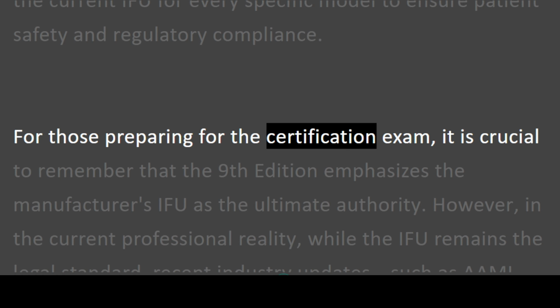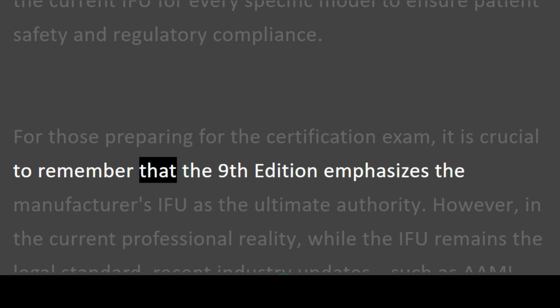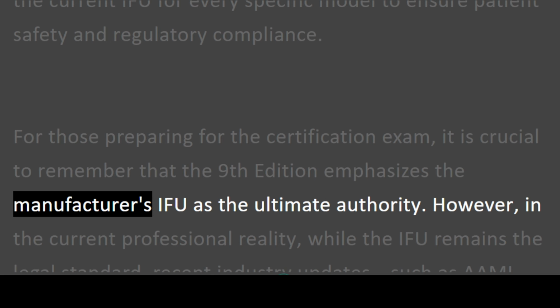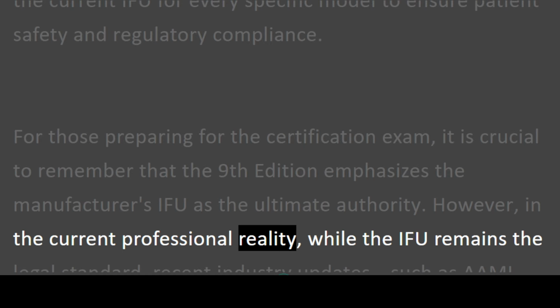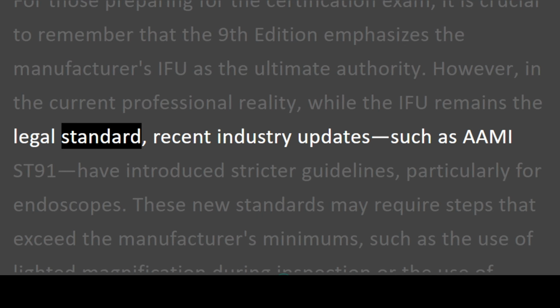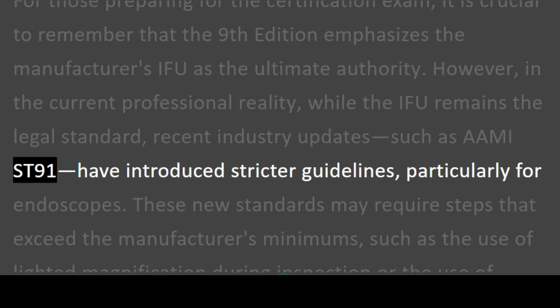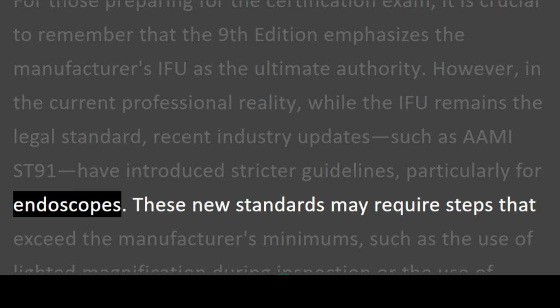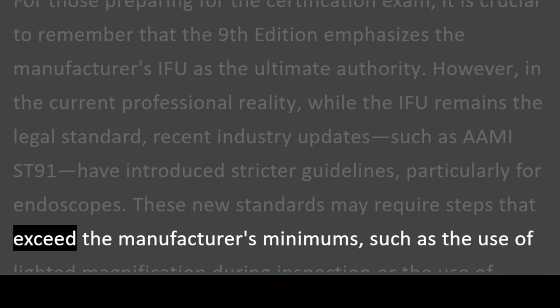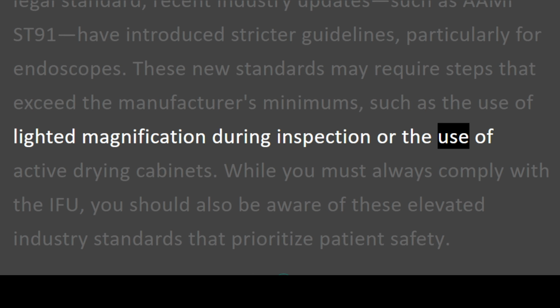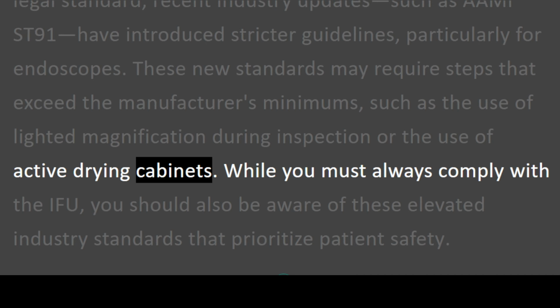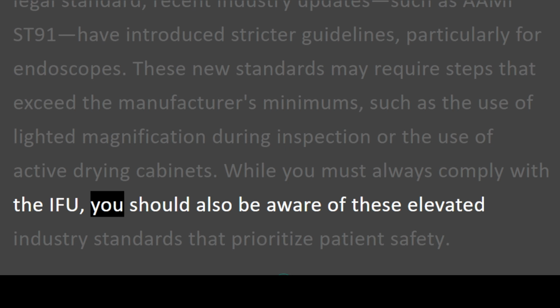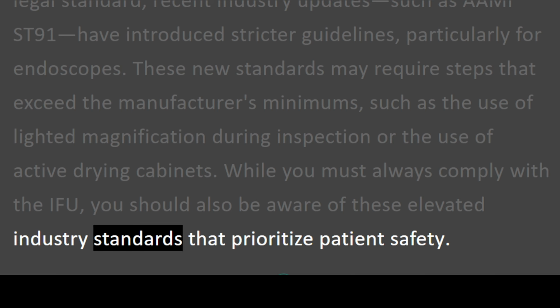For those preparing for the certification exam, it is crucial to remember that the 9th edition emphasizes the manufacturer's IFU as the ultimate authority. However, in the current professional reality, while the IFU remains the legal standard, recent industry updates, such as AAMI ST91, have introduced stricter guidelines, particularly for endoscopes. These new standards may require steps that exceed the manufacturer's minimums, such as the use of lighted magnification during inspection or the use of active drying cabinets. While you must always comply with the IFU, you should also be aware of these elevated industry standards that prioritize patient safety.